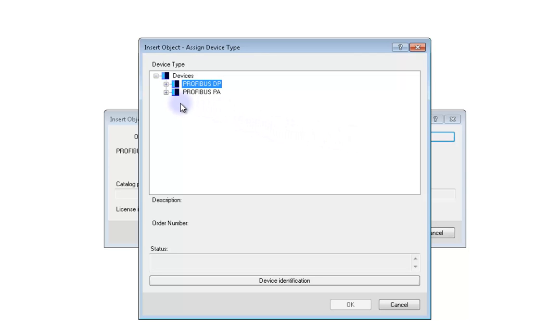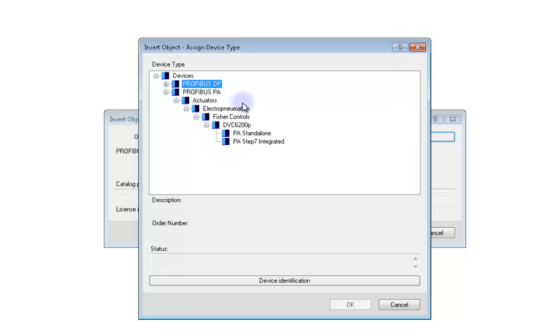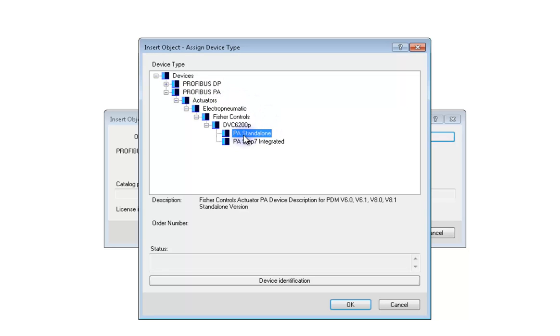Expand Devices and then Expand Profibus PA. Highlight PA Standalone. You'll never need to use the PA Step 7 integrated and it is important that you only choose Profibus PA here. Click OK.